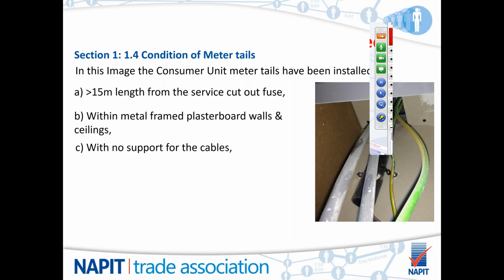There's no support on the cables, they're quite loose, and there's no reinstatement of the fire protection where it goes through that ceiling. So what do we think here? We've got a few problems with these. We're looking at section 1 on the EICR inspection schedule - the condition of the meter tails and the distributor's equipment.